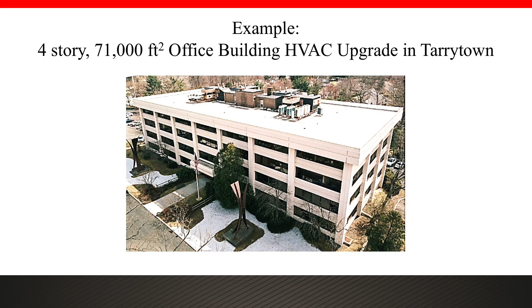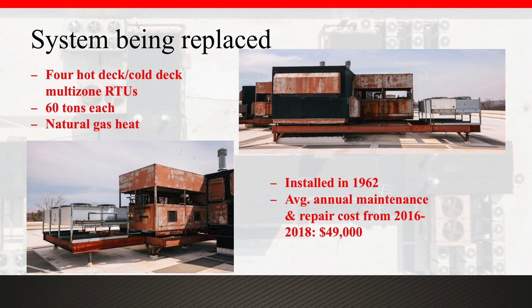If you've seen Jurassic Park, there's that scene where people are sitting in a car and the dashboard is vibrating because a T-Rex is approaching. When this system comes on, the people on the 4th floor feel the exact same way. This system is four hot deck, cold deck, multi-zone rooftop units installed 57 years ago when the building was constructed. Over the last two years, the owner has been spending around 49 grand per year in maintenance costs. So it's time for a change.